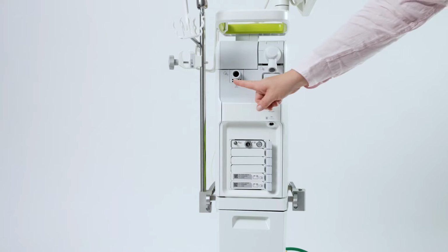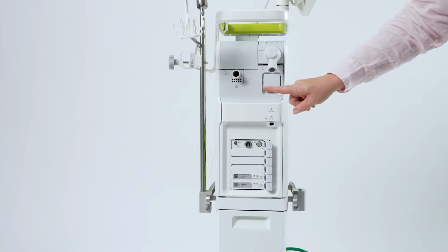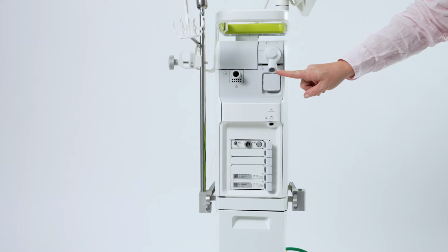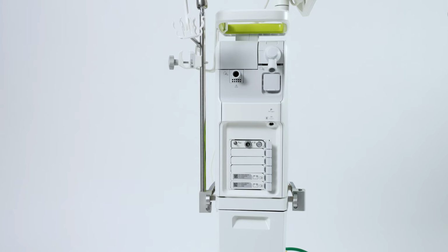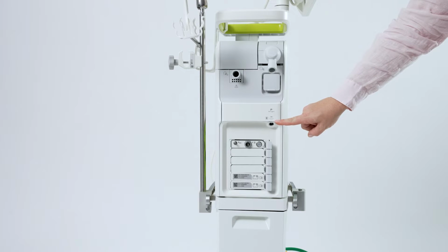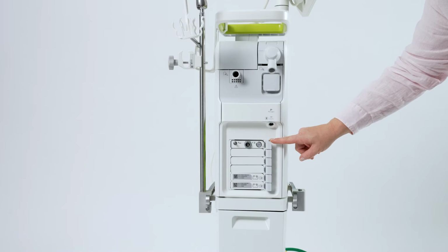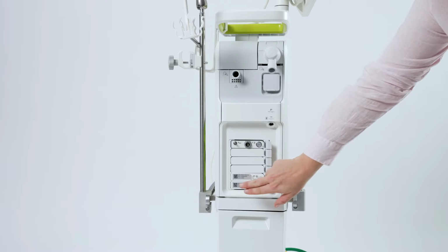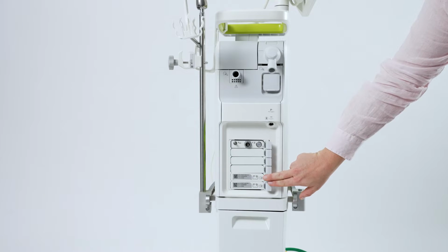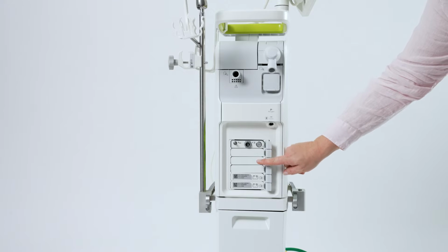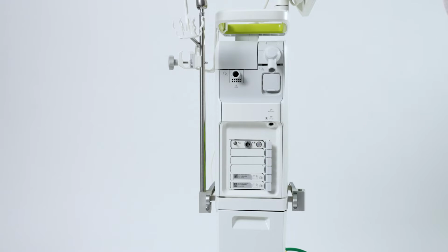Your inspiratory outlet is located here. Your expiratory inlet is located here. To hook up Aerogen technology, plug it into the Aerogen outlet located here. Here at the top is your Y sensor rack. The two bottom are your batteries. You may add modules as desired, for instance CO2 and EDI capabilities.